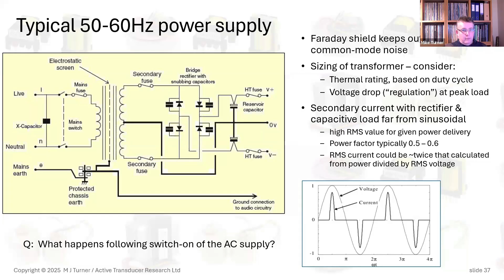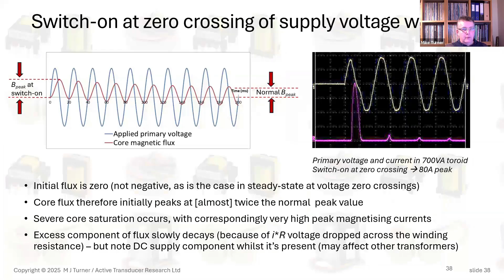The problem with that is that then the voltage on those capacitors here jumps up from nothing to the maximum value instantly, or almost instantly, limited by the impedances. So you get a blooming great thump of charging current on the capacitors. And really the only answer to that is to use some sort of current limiting arrangement. If you can't live with it and just accept the overload current for a short time, and most equipment frankly does, then you need something like that.